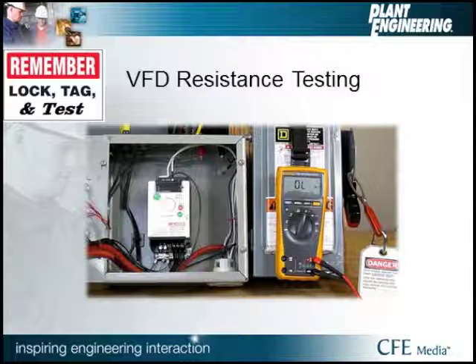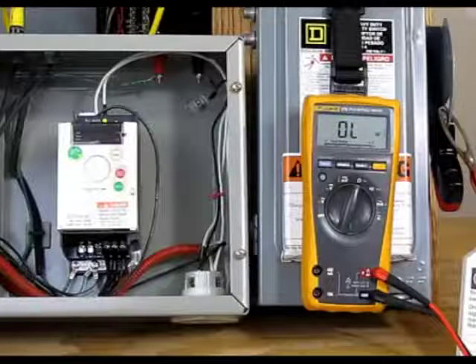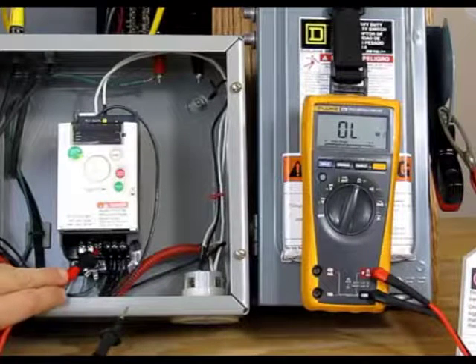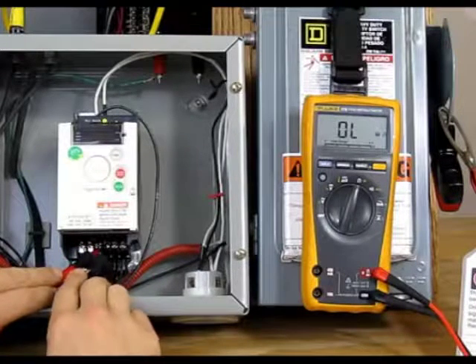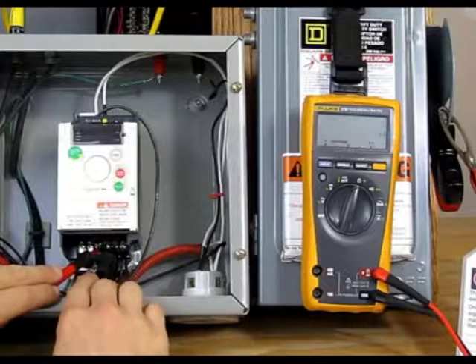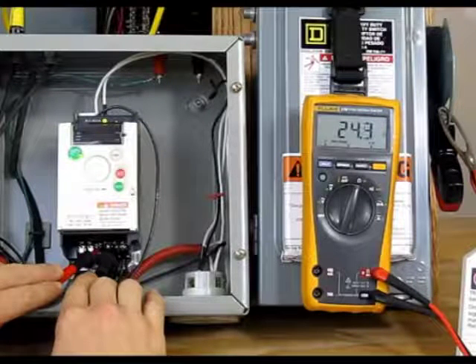In this test, we're going to be testing the same motor, but we'll be testing at the variable frequency drive. This resistance test is also being done to diagnose the windings of a motor. However, this test is being performed from the VFD that feeds the motor. This is useful when we don't have access to the motor itself.